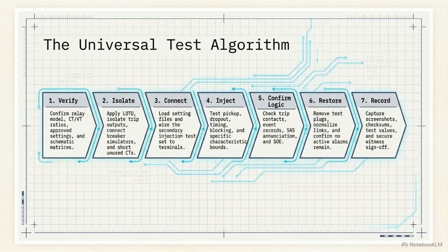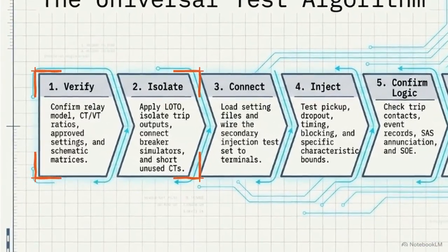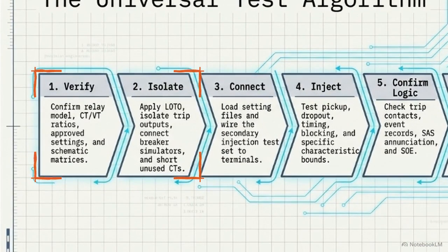Every single module in the 41 test commissioning framework follows the universal test algorithm, a mandatory 7-step operational procedure. Steps 1 and 2, verify and isolate, involve loading approved engineering setting files and verifying internal logic checksums. This mathematical algorithm ensures that the relay's configuration code remains uncorrupted. Once the data is confirmed, the team applies LOTO and verifies the isolation of all outputs.